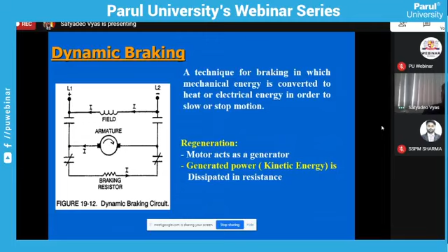Dynamic braking in VFD. Basically, in VFD, there are two sections. One is the converter section or rectifier section, and the second one is the DC bus, capacitors, then inverter. First, AC is converted into DC. Then DC is again converted into AC for driving the motor. In between the link, there is one IGBT and a regeneration resistor.